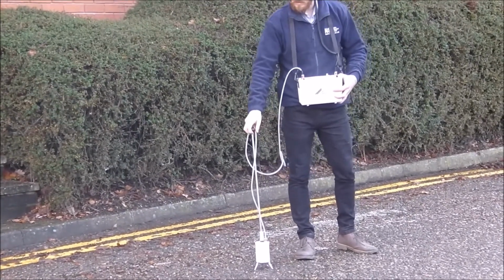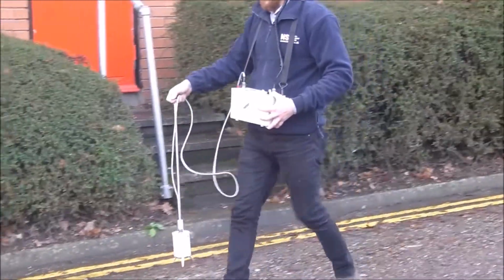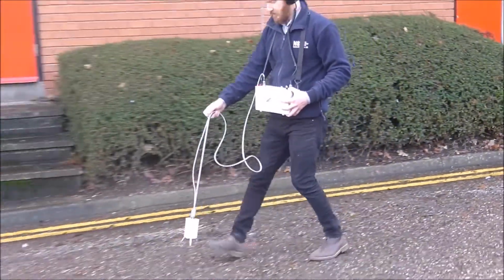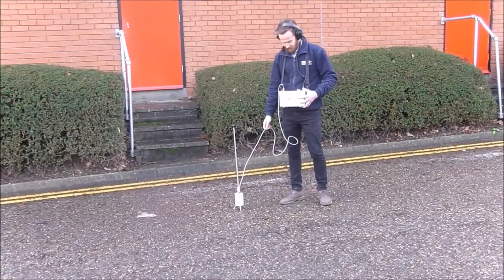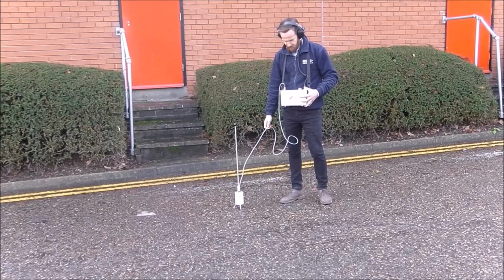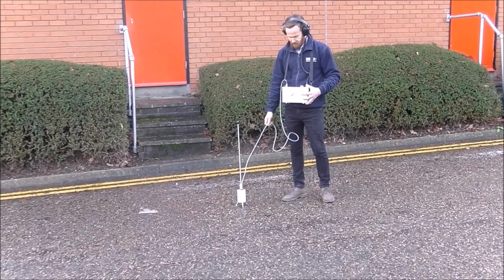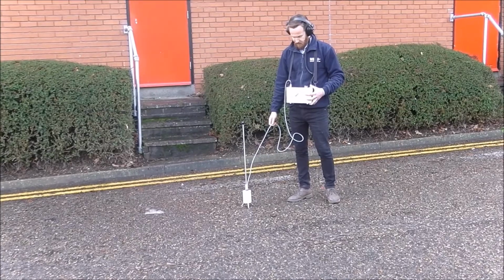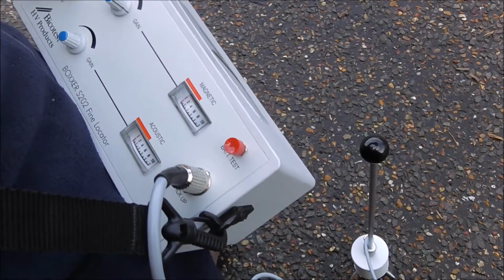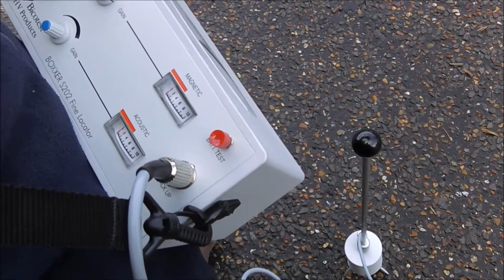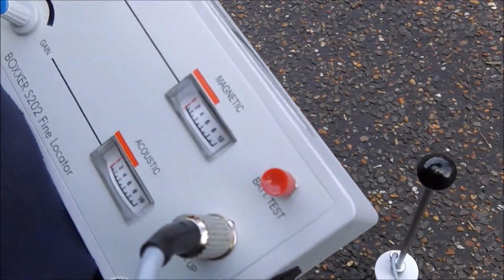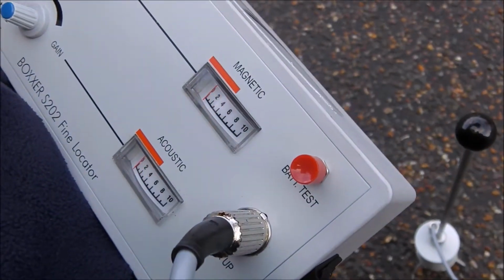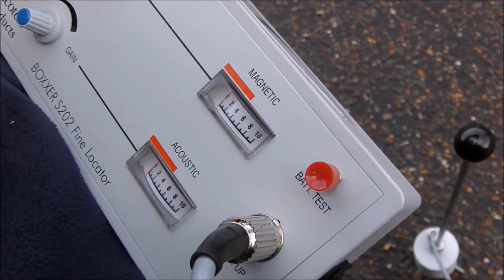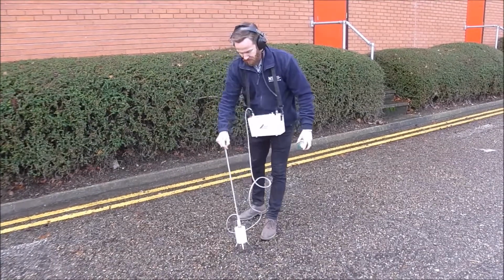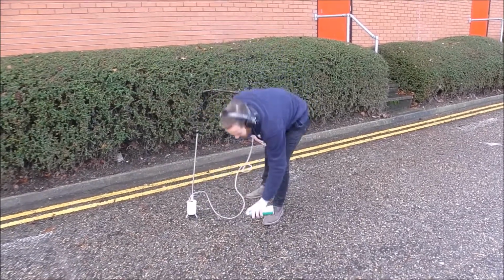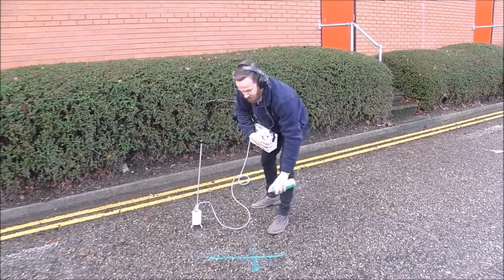Search the suspected fault area using the acoustic pickup with sufficient gain until the acoustic signal from the fault is detected. This is identified by being repeatedly coincident with the magnetic signal. Using the gain control, the position of maximum acoustic signal may now be determined and hence the position of the fault. As small changes in signal level may not be recognised on the headphones, it is preferable to use the meter for this determination. The acoustic pickup should be placed on the ground and not held, since small movements of the pickup will generate noise.